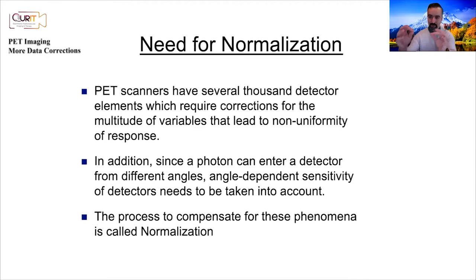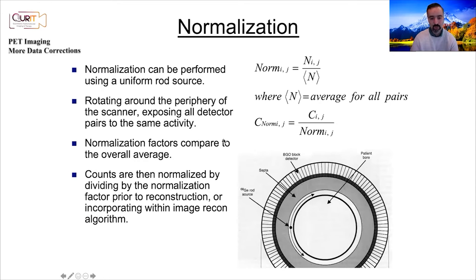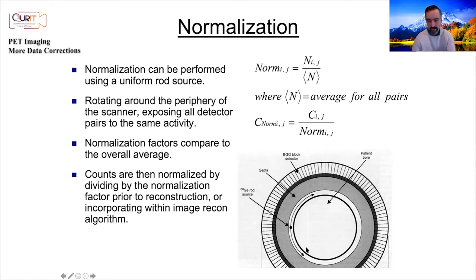The sensitivities of individual crystals vary from day to day, week to week, month to month, and there are also angle-dependent sensitivities. This correction is called normalization, and it is often performed using a uniform rotating rod source that rotates around at the periphery of the field of view, because pretty much all lines of response pass through it.